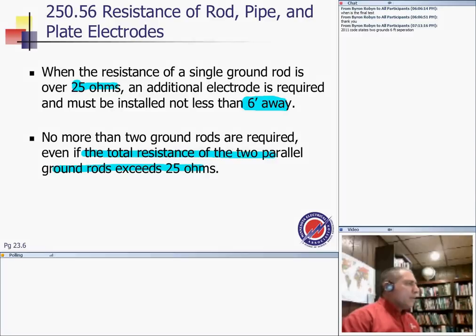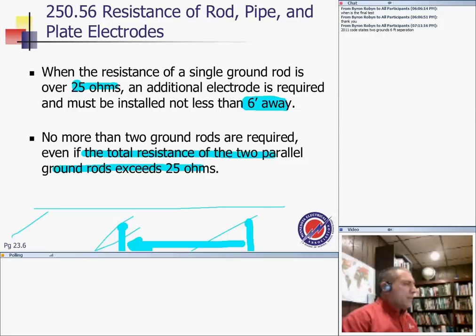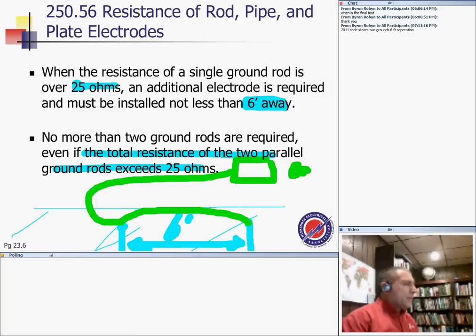So here's your underground stuff, my friend, and you grab your rod. You put your rod number 1 here, and you got water to your building, so you drive another rod. When you add the second rod, they don't want you to put them closer than 6 feet, because if you get them closer than 6 feet, it doesn't get you a whole lot. It doesn't reduce your resistivity. You tie them together, and then you run all the way to the panel, to the bar in the panel, the equipment grounding conductor. Excuse me. Any questions about the rods?